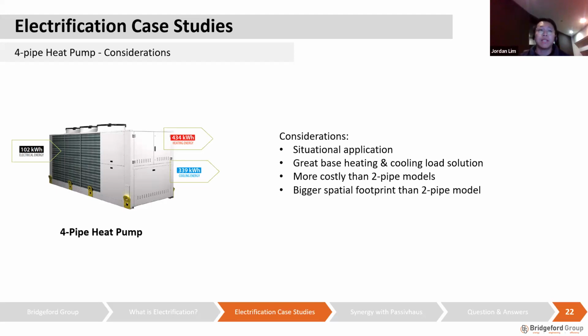The spatial footprint is higher than a typical 2-pipe heat pump model. It is also slightly more costly because of the dual functionality, but as mentioned earlier, it can be really good in certain circumstances.